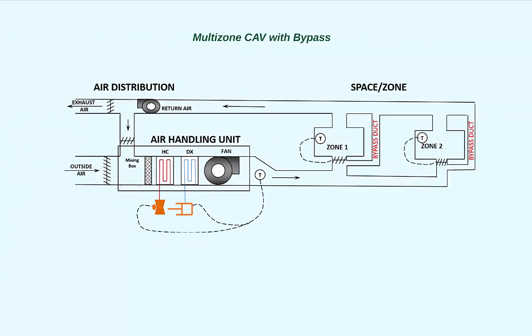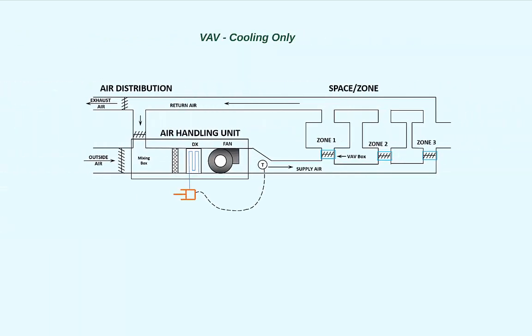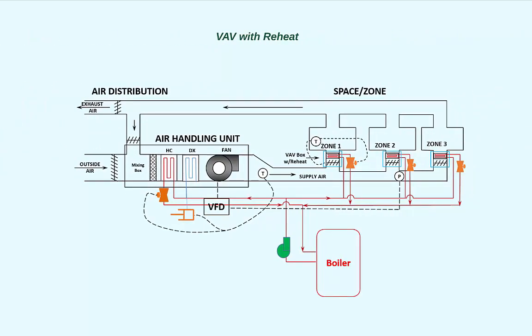The same control is used for multi-zone constant air volume with bypass. The DX unit is controlled based upon discharge air temperature. Unneeded heating or cooling is bypassed around the zone. When it comes to variable air volume systems, the control is exactly the same as multi-zone constant air volume systems. The DX unit cycles based upon discharge air temperature. This is true for cooling only VAV systems, shown here, or VAV cooling with zone reheat. There is one potential problem that may arise with VAV systems that you should be aware of.